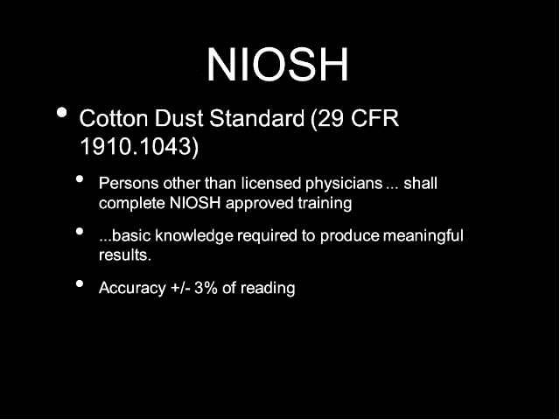NIOSH was also the first standard to designate what was acceptable for accuracy. They said a device had to measure a volume from 0 to 12 liters with an accuracy of 3% of the reading. And several devices at that time were rather proudly boasting that they had accuracy of between plus and minus 5 and 10%. So it obviously was needed to tighten up the accuracy to make sure that we were getting better results.